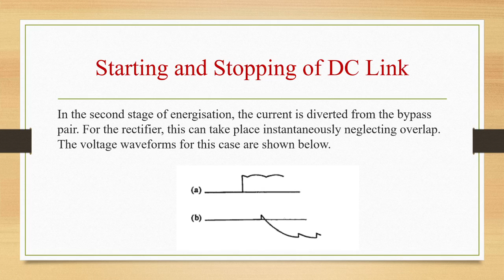So we have to note a point that, to avoid operation at high delay or extinction angles, de-energization of a bridge at the rectifier or inverter station is accompanied by the de-energization of a bridge at the inverter or rectifier station. Let us see the startup of a DC link.